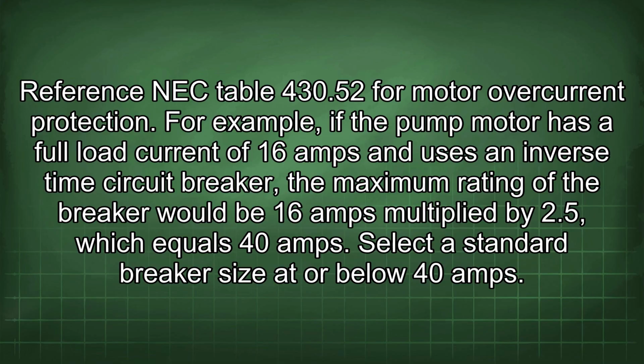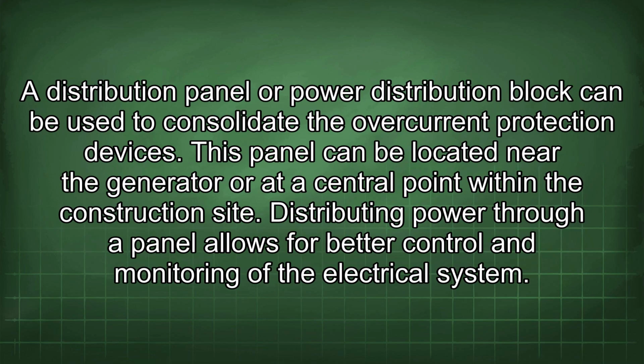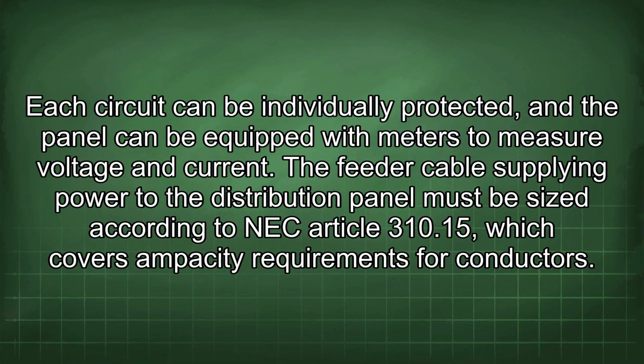For example, if the pump motor has a full load current of 16 amps and uses an inverse time circuit breaker, the maximum rating of the breaker would be 16 amps multiplied by 2.5, which equals 40 amps. Select a standard breaker size at or below 40 amps. A distribution panel or power distribution block can be used to consolidate the overcurrent protection devices. This panel can be located near the generator or at a central point within the construction site. Distributing power through a panel allows for better control and monitoring of the electrical system. Each circuit can be individually protected, and the panel can be equipped with meters to measure voltage and current.